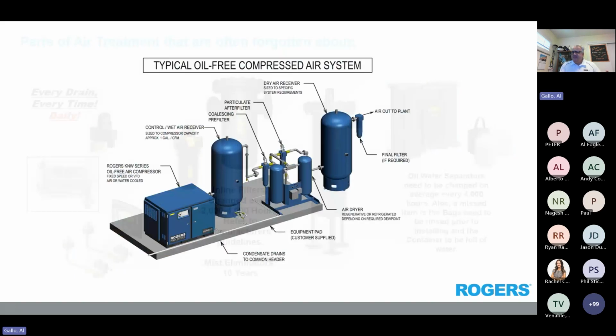And because I didn't have a picture of a desiccant dryer and the layout of a desiccant dryer, I thought this was really good. This was right from one of the Rogers earlier webinars. So you got your oil-free air compressor, you got a wet receiver, that's that first tank, which is then going through a coalescing pre-filter, then to the desiccant dryer, and then out through a general purpose filter, and then into a dry tank, and then out to the system. And if they needed an activated carbon filter for whatever higher filtering, they can do that.